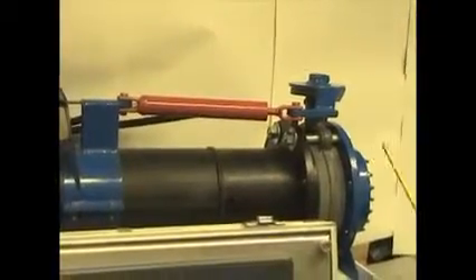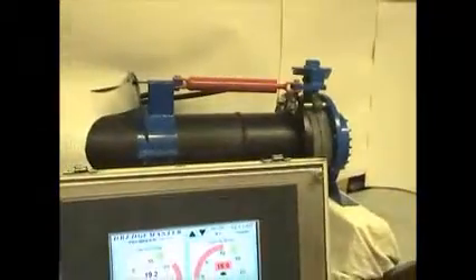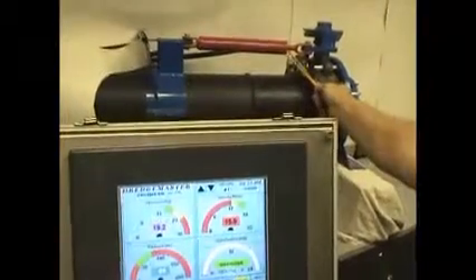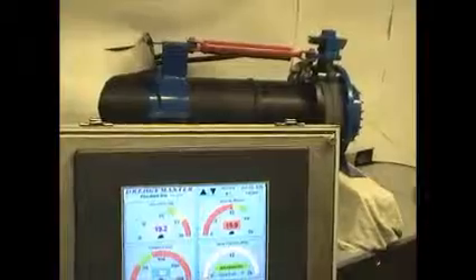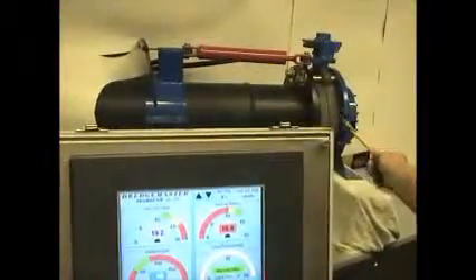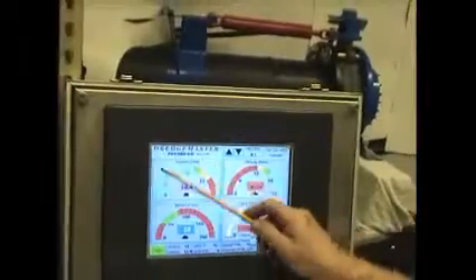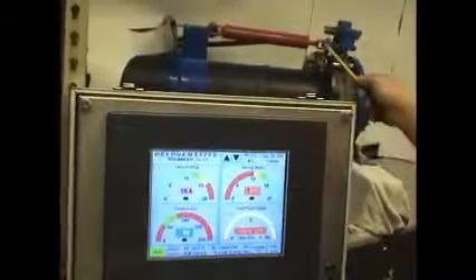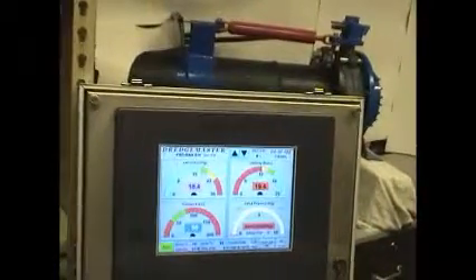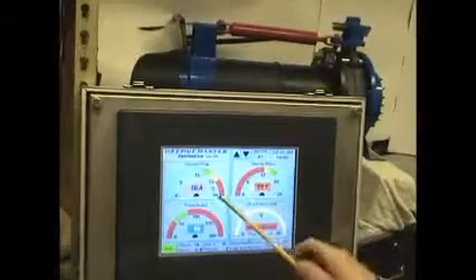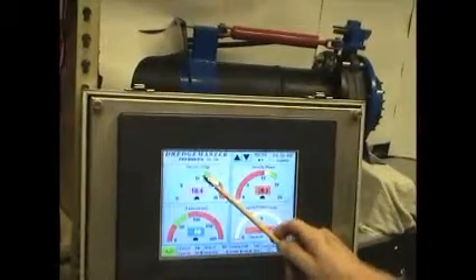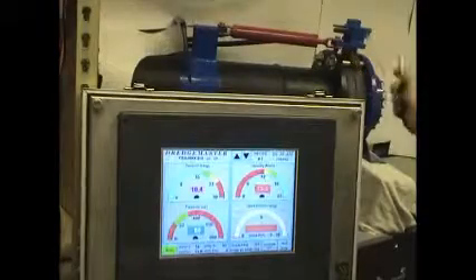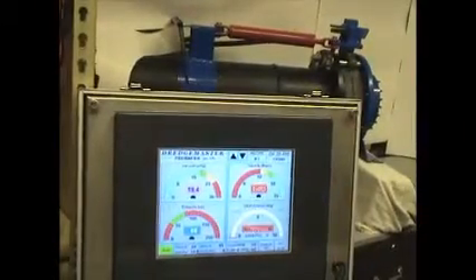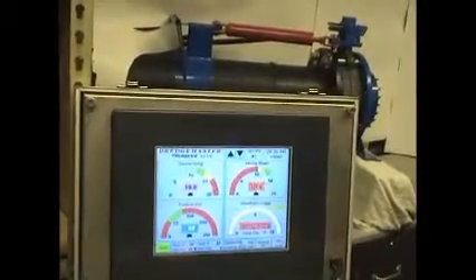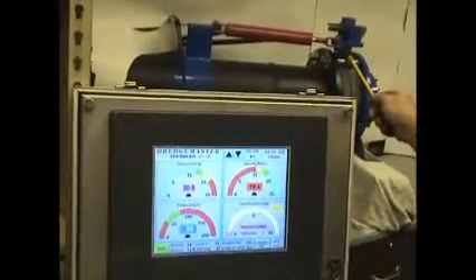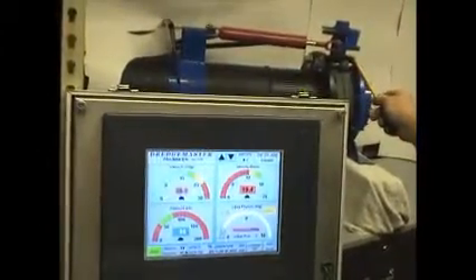We're going to demonstrate how the valve actually opens up. So what you see here is in relation to what the cylinder is doing under the water, opening up the butterfly valve in here. So let's look at the vacuum gauge here and watch the cylinder at the same time so you can see what actually happens under the water. As you can see, our vacuum is in the green zone. Our cylinder is fully closed. Our vacuum is starting to increase. Once it starts to get into the yellow zone, you can see our cylinder is starting to step itself open.